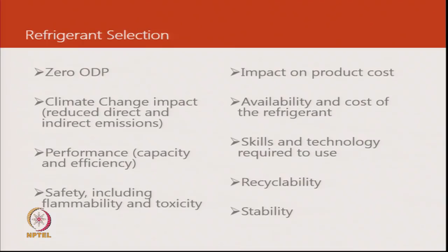People who are used to the earlier HCFCs and CFCs in manufacturing and service never really were concerned about short exposure to air. Air, as you know, contains some moisture, and some of the newer lubricants that are used in HFCs have a high affinity for moisture. Short exposure to the ambient air, like leaving the compressor open or the system open to air, leads to the hygroscopic oil taking a lot of moisture and changing its viscosity, and that leads to performance impact as well as reliability impact. So, there is a compromise on the life of the air conditioner as well as the performance.